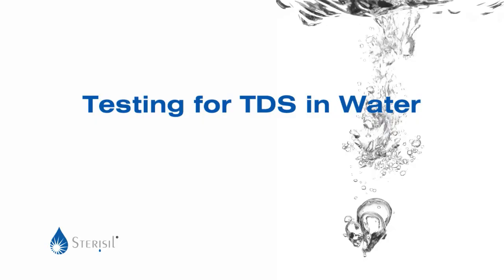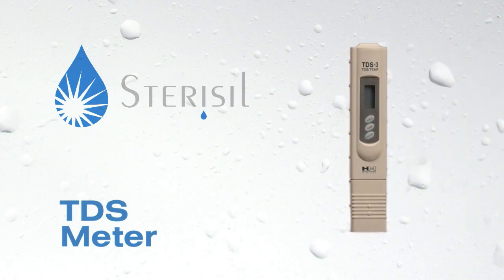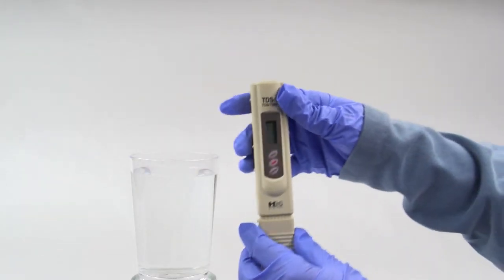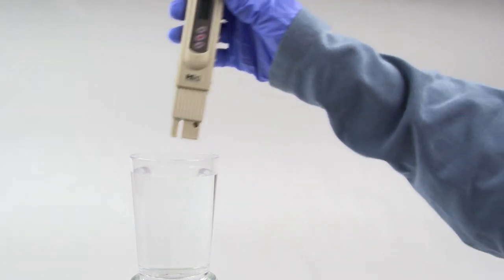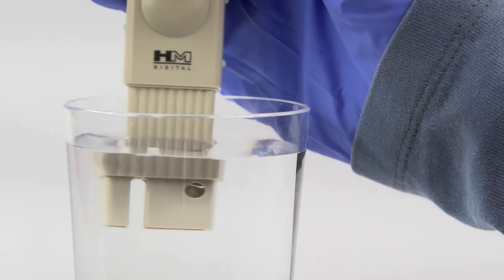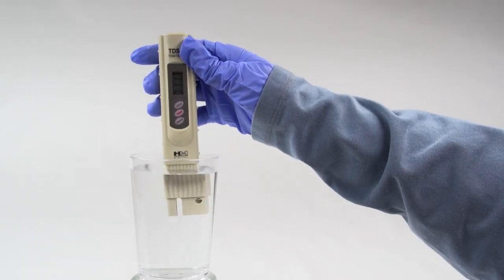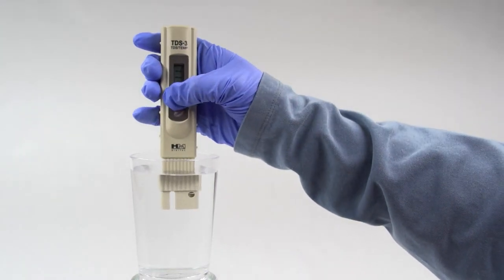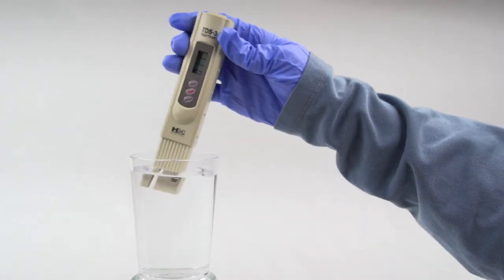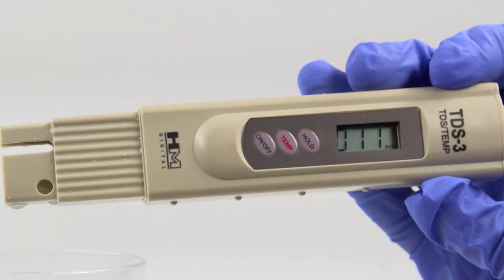To read water hardness with all Sterisil products other than the Sterisil system, use the handheld TDS meter. To measure the total dissolved solids in your water, remove the protective cap from the meter and press the on-off button. Immerse the sensor in your water sample up to the ribbed section on the meter and gently stir to dislodge any air bubbles. Wait about 10 seconds for the display to stabilize and press the hold button to read the display out of the water. Shake excess water from the sensor and replace the cap.